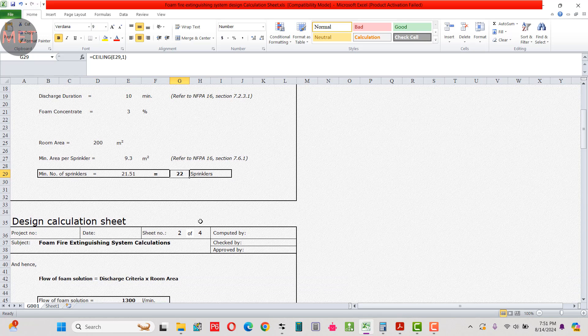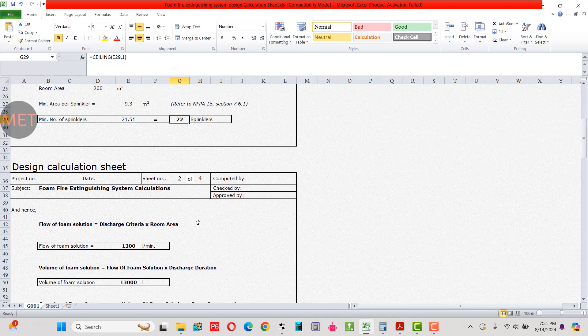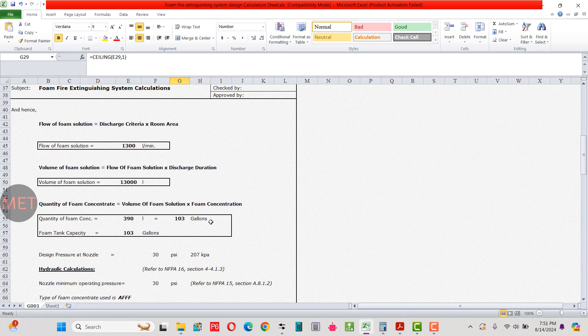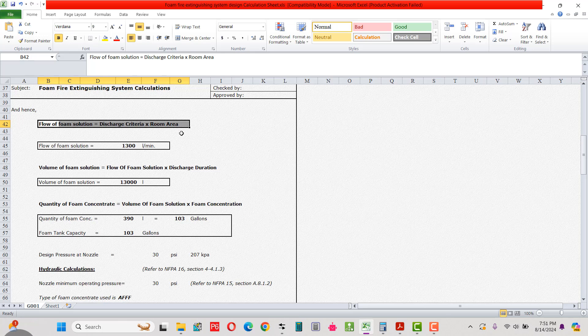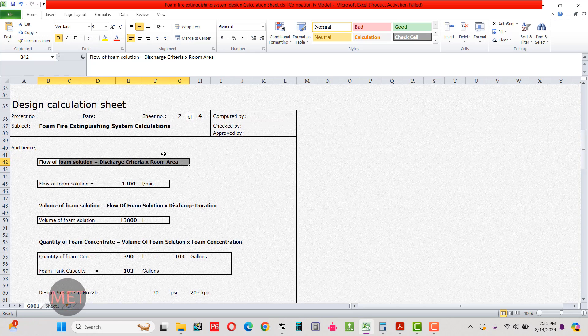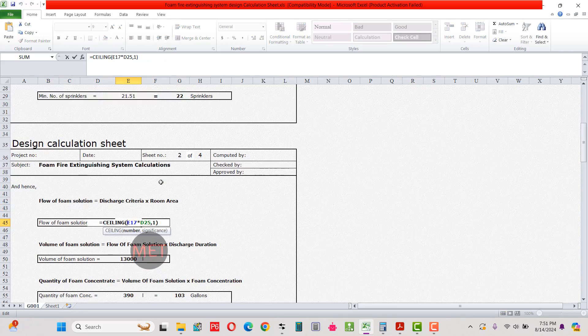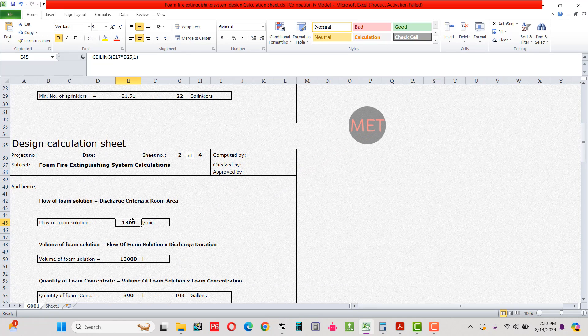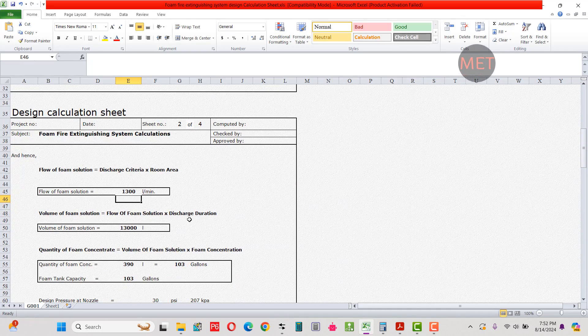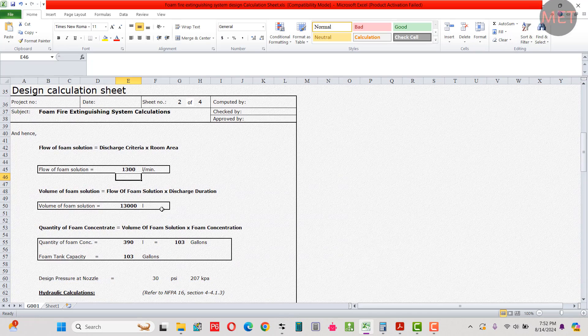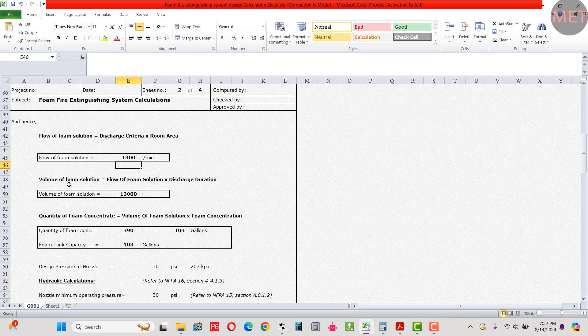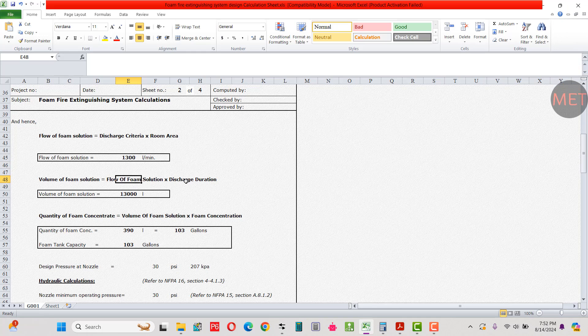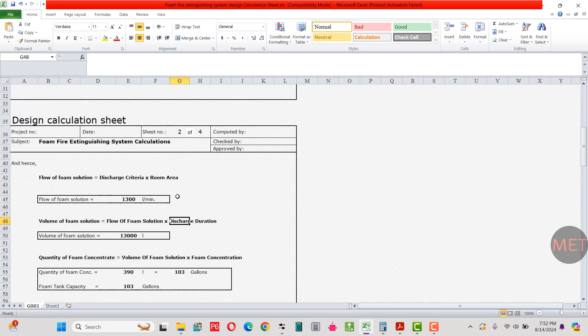Now we calculate the foam tank capacity. First, we calculate the flow of foam solution, which equals discharge density multiplied by area: 6.5 liters per minute per square meter × 200 square meters = 1300 liters per minute. Then the volume of foam solution equals flow × discharge duration: 1300 × 10 minutes = 13,000 liters.